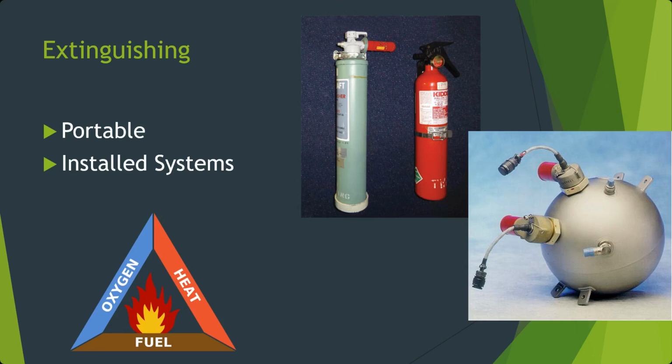Why doesn't water work on oil? Grease fires. Oil floats on the water. So the water goes to the bottom, the oil comes to the top, and it doesn't do anything. The dry powder that we use is going to sit on top, or the carbon dioxide foam is going to sit on top. In fact, putting water on an oil fire makes it worse because it vaporizes and throws the oil everywhere and atomizes it and causes it to become explosive.